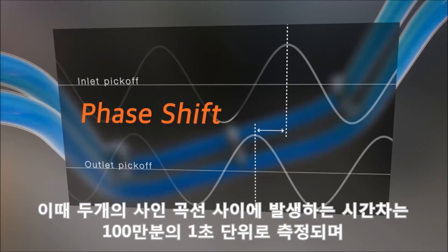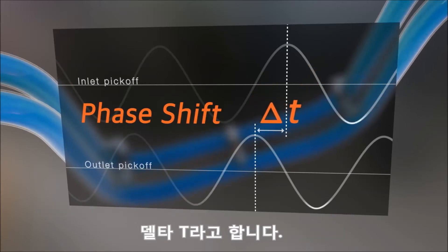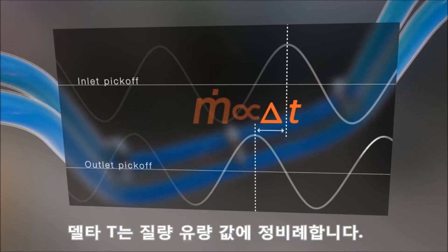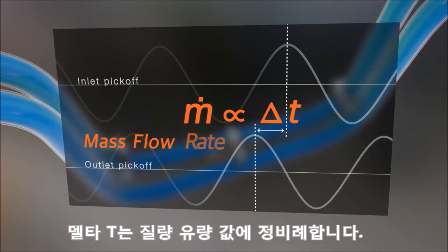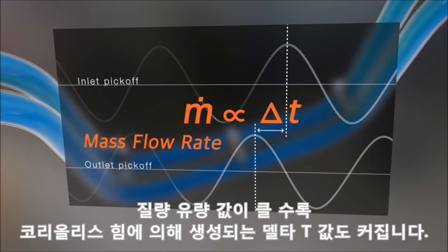The time delay between the two sine waves is measured in microseconds and is called Delta T. Delta T is directly proportional to the mass flow rate — the greater the Delta T created by the Coriolis force, the greater the mass flow rate.